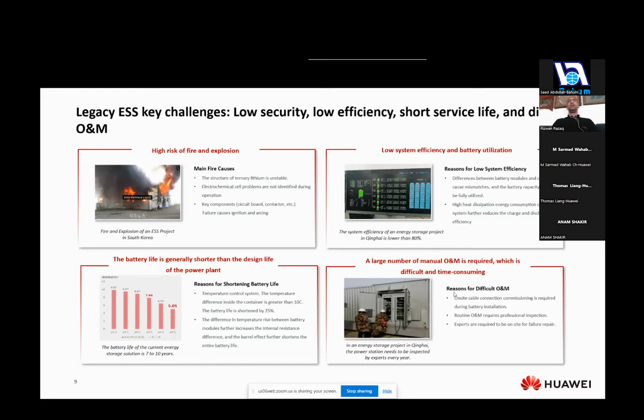The second aspect is the low system efficiency and battery utilization. The reason for that is the efficiencies of multiple battery cells being interconnected in series without optimizers being included within the battery packs. The other factor is the battery life. Typically, if you're not utilizing it in the optimum method, you will have as low as 5 years, and in some cases with other types of batteries, even less than that. And the last factor is the large amount of manual O&M required for energy storage projects in order to do the recalibration of the battery packs themselves.